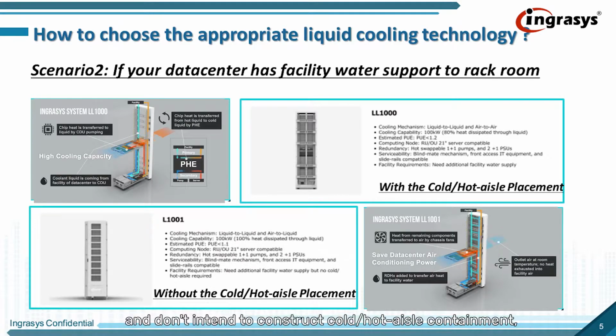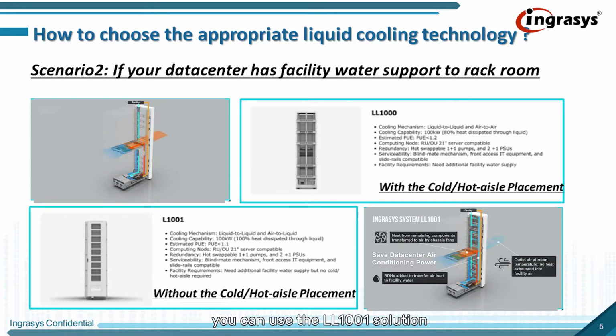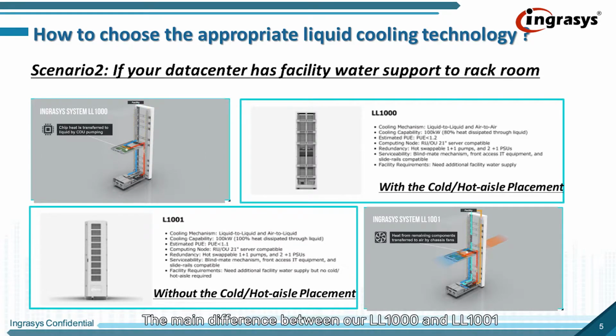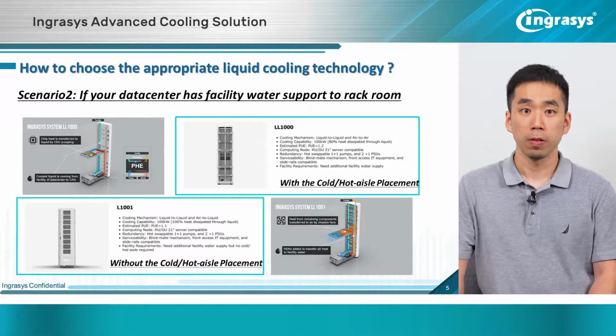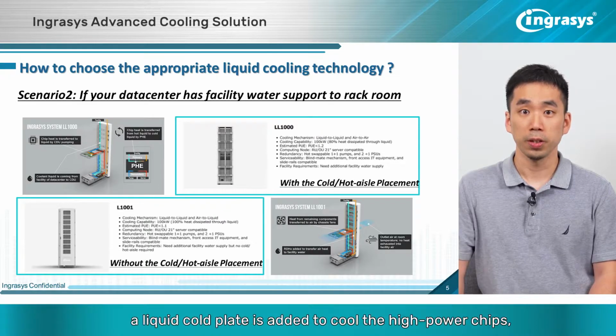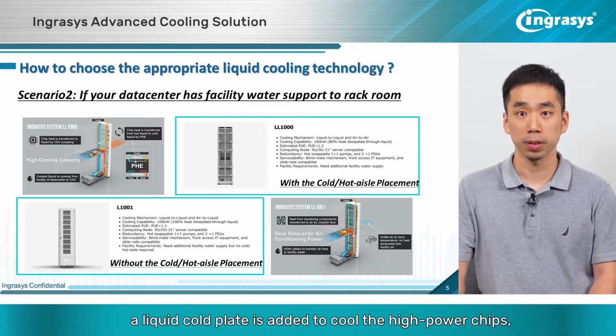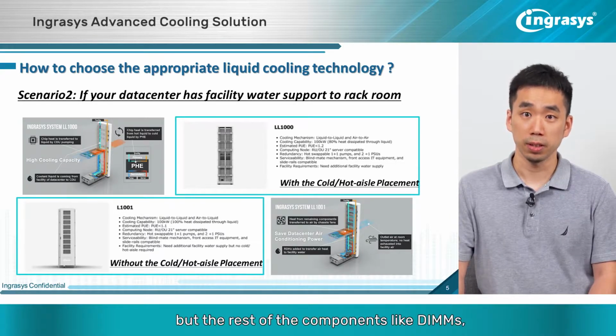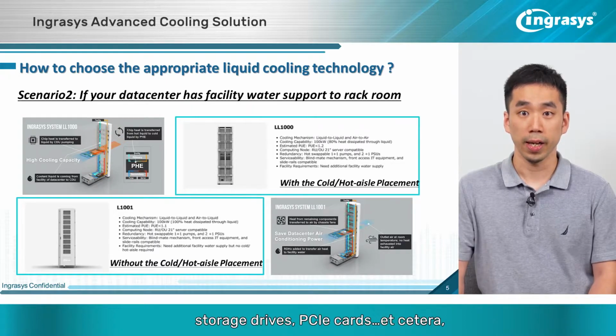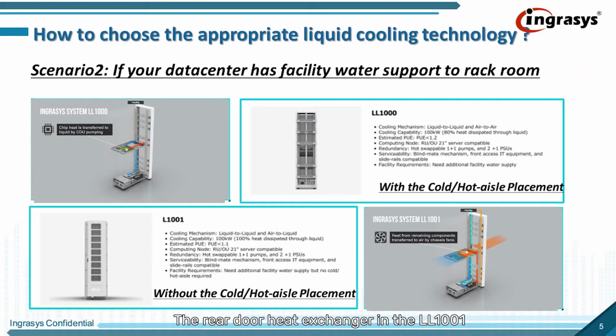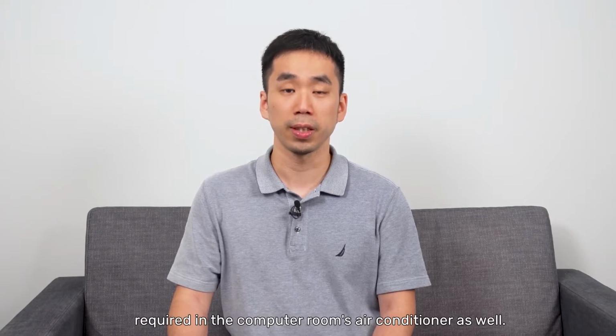If you don't have and don't intend to construct cold and hot aisle containment, you can use the liquid-to-liquid 1001 solution for easy deployment. The main difference between our liquid-to-liquid 1000 and the liquid-to-liquid 1001 is the rear door heat exchanger. For the direct-to-chip liquid cooling solution, a liquid cold plate is added to cool the high-power chips, but the rest of components like DIMMs, storage drives, PCIe cards, etc. still utilize air cooling. The rear door heat exchanger in the liquid-to-liquid 1001 uses facility water to cool the hot air so its exhaust is at neutral room temperature. It reduces the power required in the computer room's air conditioner as well.